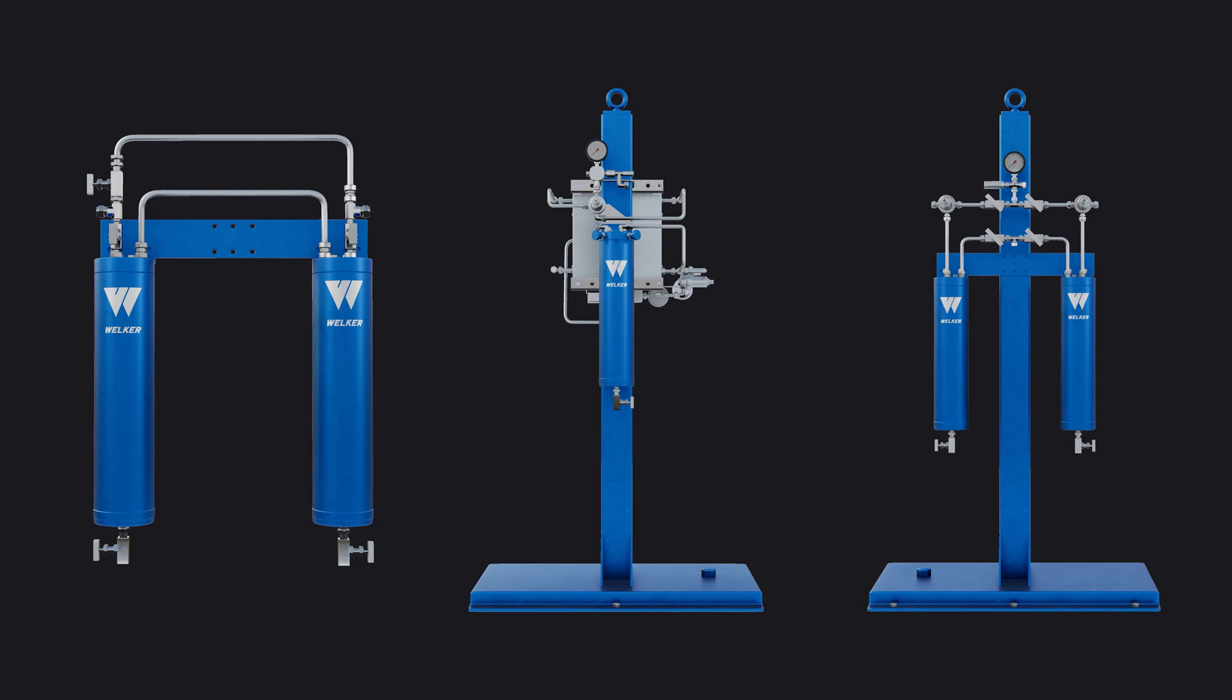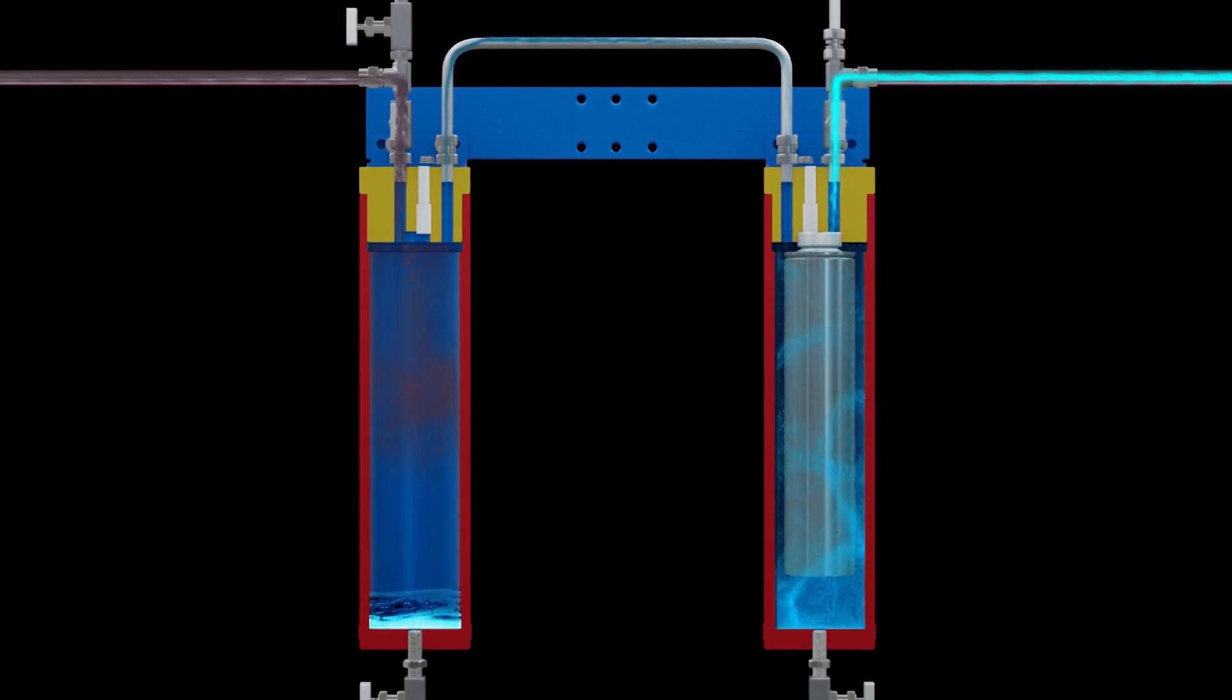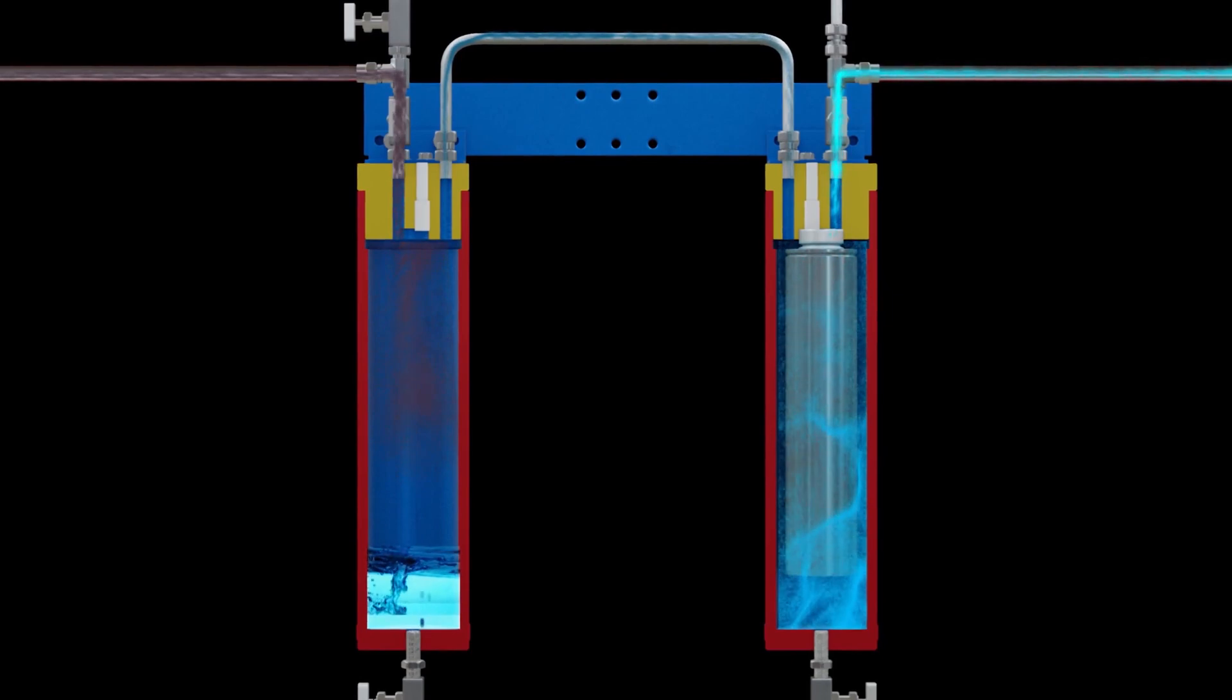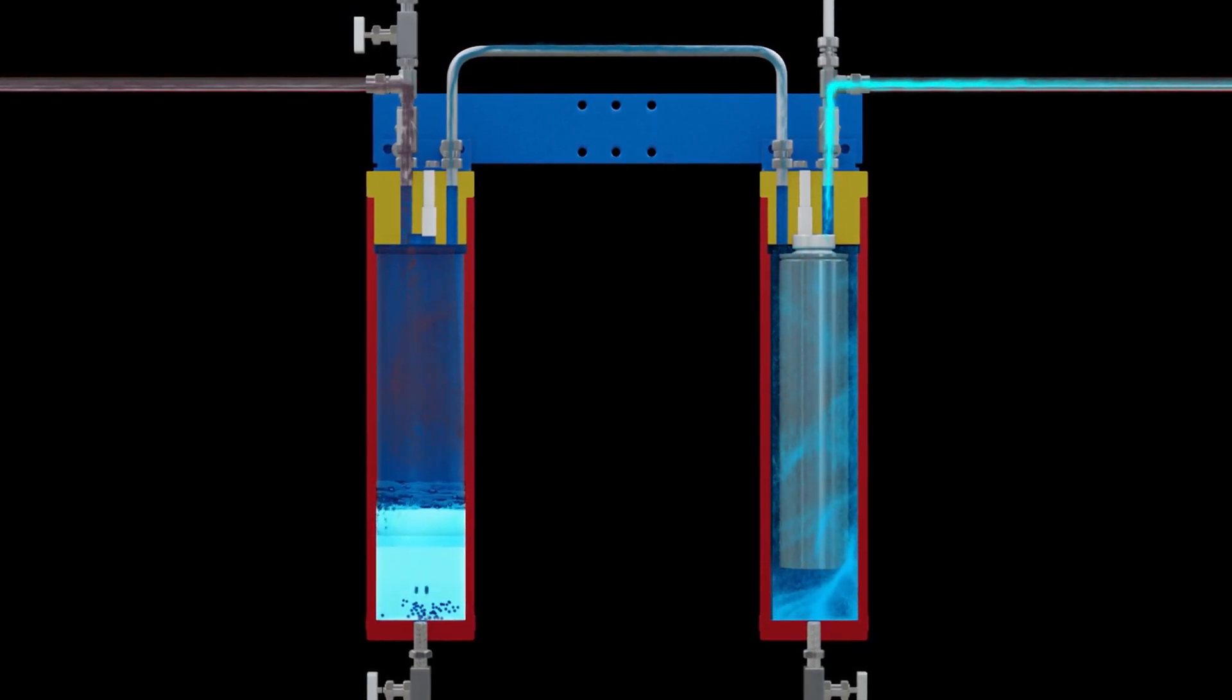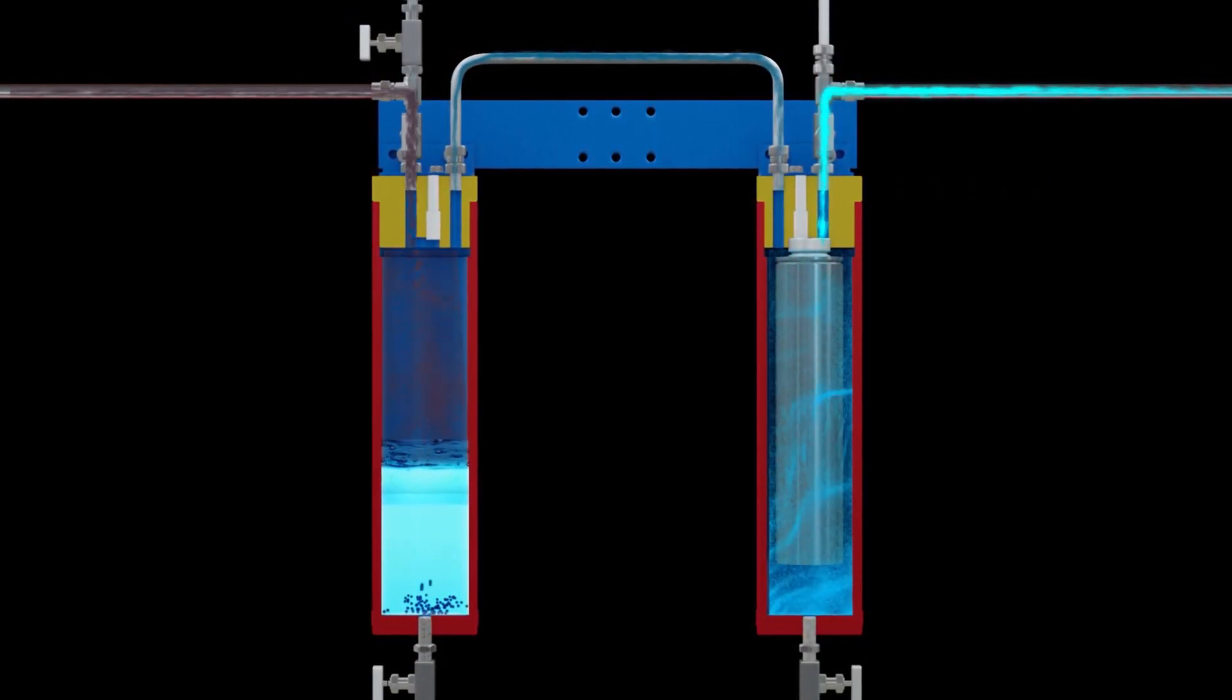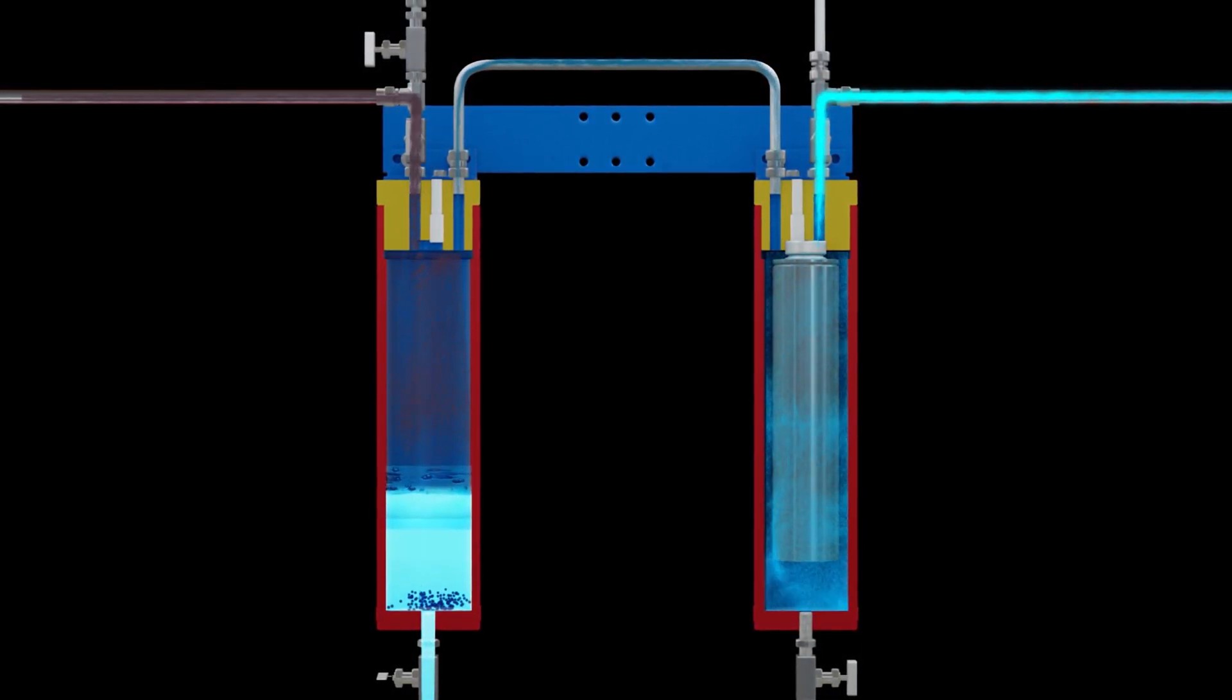The Clean Flow Basic offers contaminant and liquid removal. Pipeline gas flows freely through the liquid dump, but aerosols and free liquids are separated from the stream. The filter dryer removes contaminants from the dried gas before feeding the downstream instrument. Gravity causes the separated liquids to fall to the bottom of the liquid dump where they collect until the unit is drained.